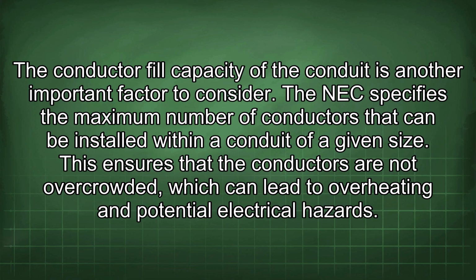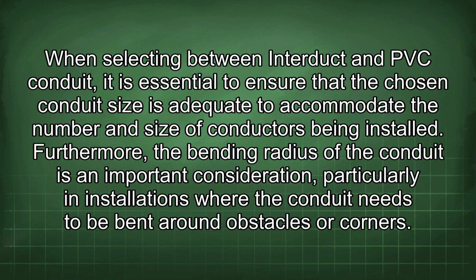The NEC specifies the maximum number of conductors that can be installed within a conduit of a given size. This ensures that the conductors are not overcrowded, which can lead to overheating and potential electrical hazards. When selecting between Interduct and PVC conduit, it is essential to ensure that the chosen conduit size is adequate to accommodate the number and size of conductors being installed.